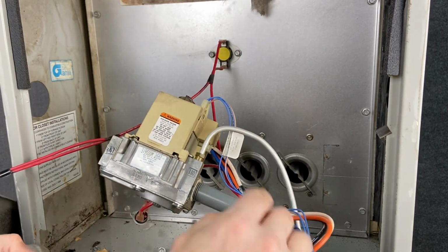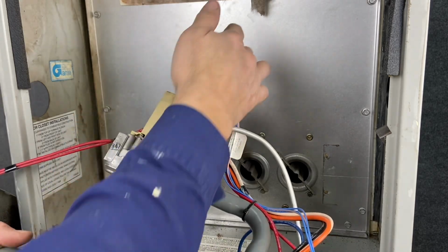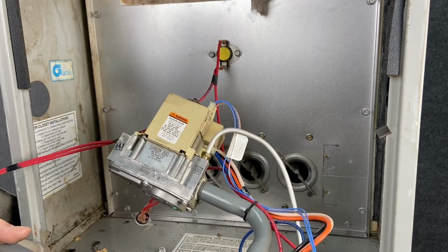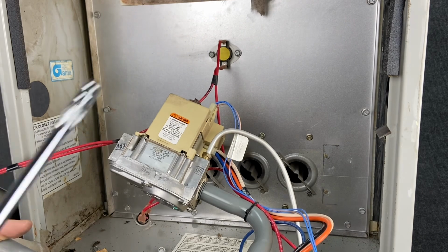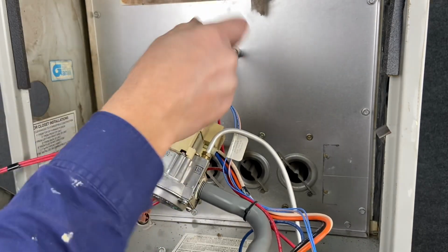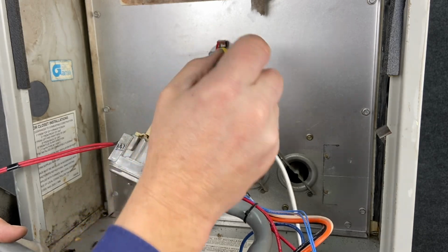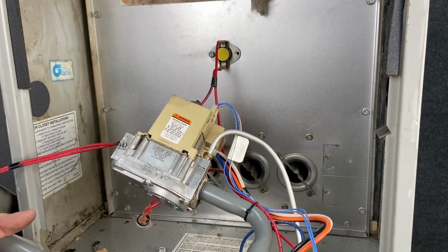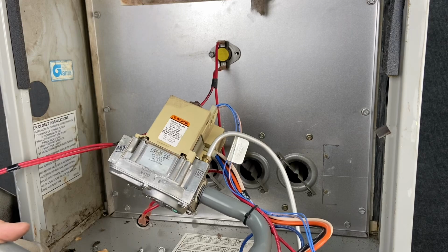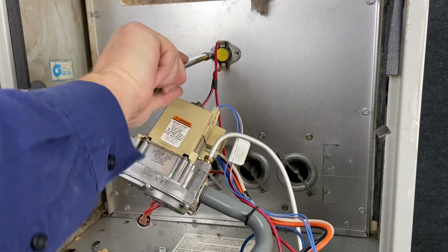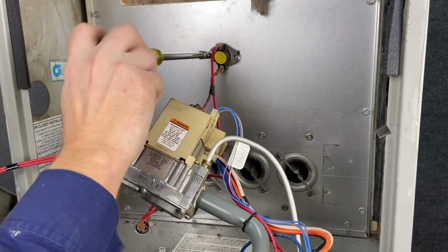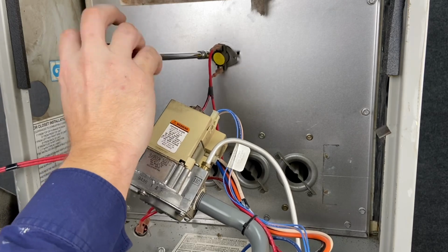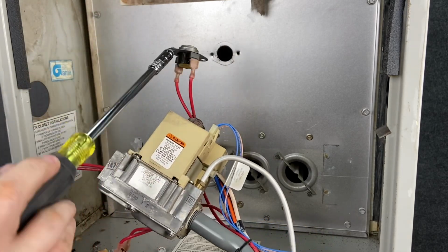But we have one set of wires right here, and this is what I want to point out. This is our primary limit switch. So I'm going to go ahead and undo the wires for that as well. This limit is going to trip because of overheating by airflow. So if this switch is tripping on you, you need to be thinking immediately airflow, airflow, airflow. For some reason, so many new techs keep thinking that it's a gas problem or it's overheating because there's too much fuel in there, and that's not true. It is going to be an airflow issue.